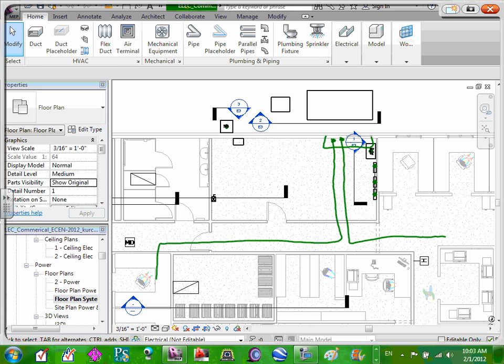We asked for 1 flow switch, so I would assume that it's probably 1 big zone. Let's do this over again. So let's say it's 1 zone, and it basically splits off. So it feeds that end of the building, that end of the building. There's a pipe coming up into the higher part of the mechanical room, and then it goes out and feeds all of the sprinklers throughout the building.